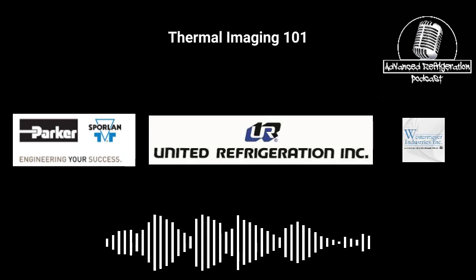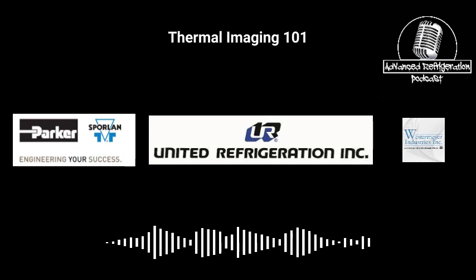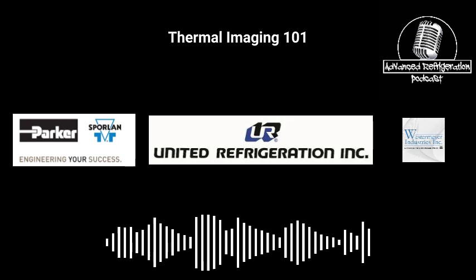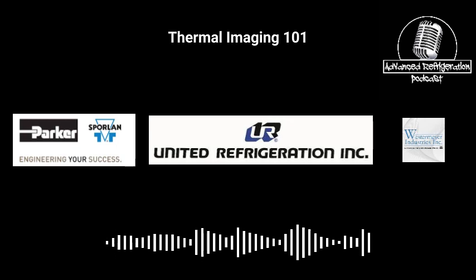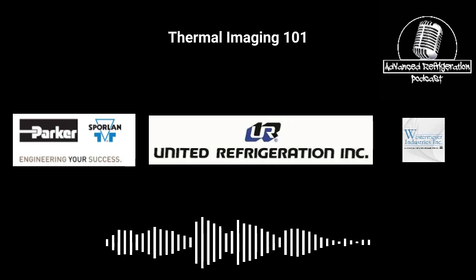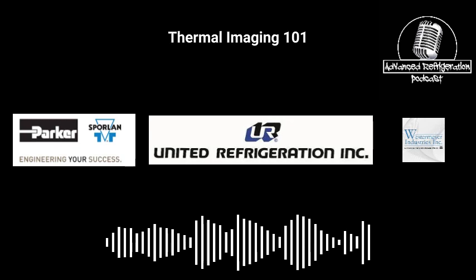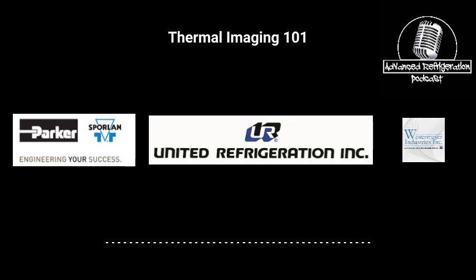So what are some other uses you've seen the thermal imager used for? One of my favorites is door frame heaters. When you're doing a PM and troubleshooting door frame heaters, you could literally walk the whole aisle instead of going through each one with a contact thermometer or contact pen checking that they're working and warm. You can scan the whole aisle by walking, finding bad doors where the argon seal has been lost or the heaters are out, before it starts sweating.